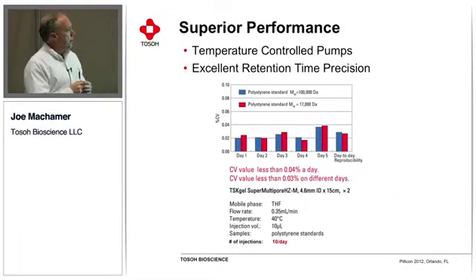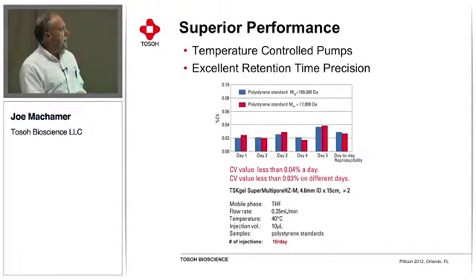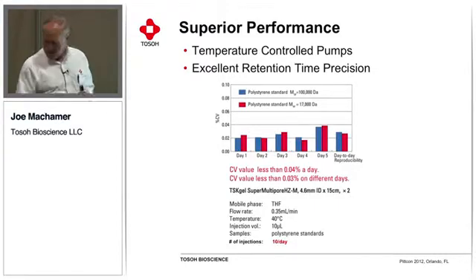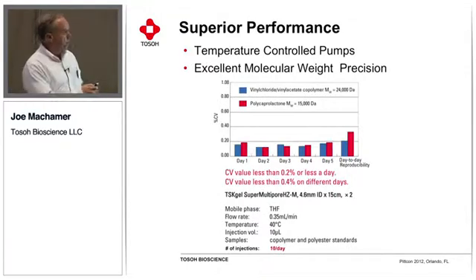And here are some charts showing reproducibility data, done on polystyrene standards. Basically, what we're seeing with these temperature-controlled pumps is excellent retention time precision. CVs for retention time are on the order of less than 0.04% a day. When you translate that into molecular weight precision, molecular weight CVs can be 0.2% or less on a day.